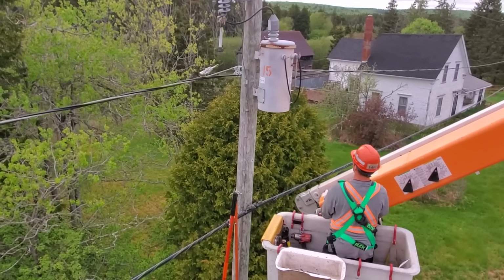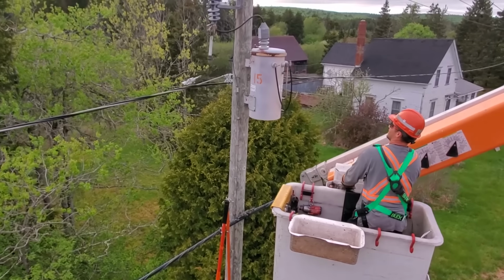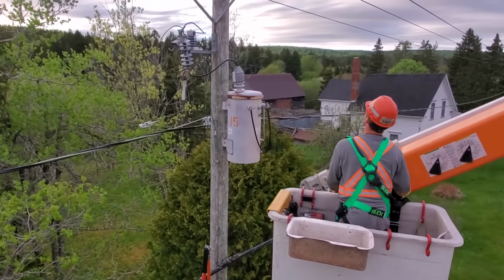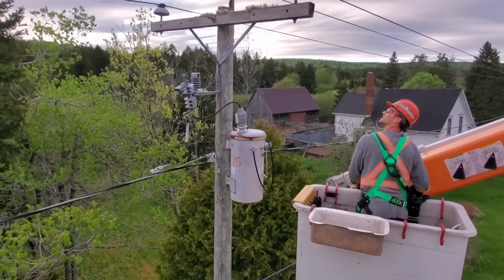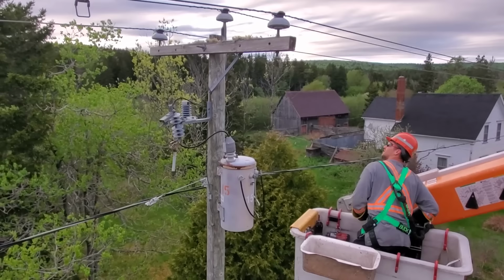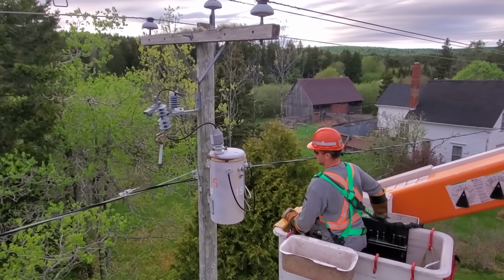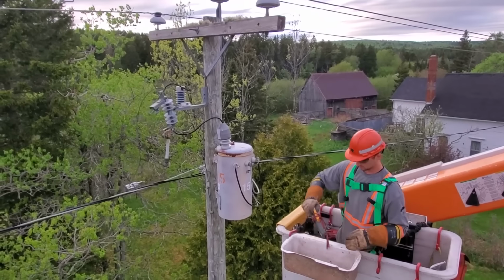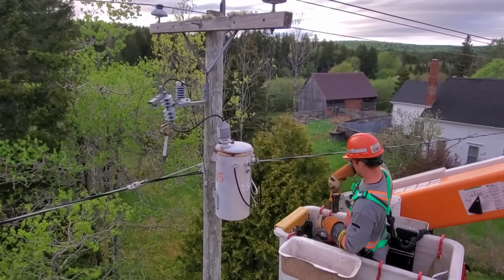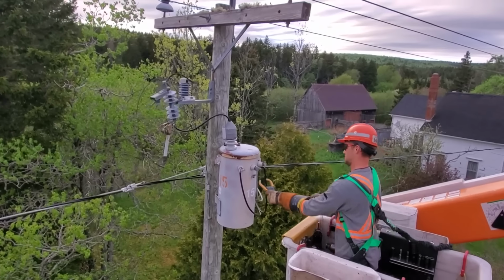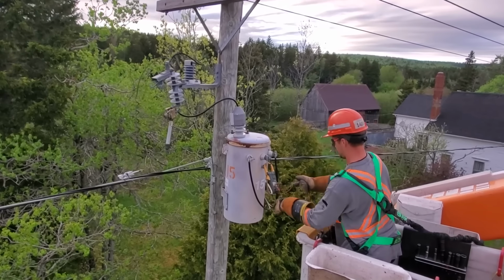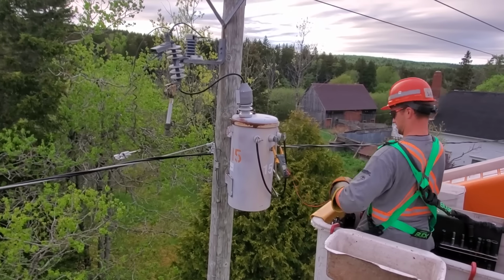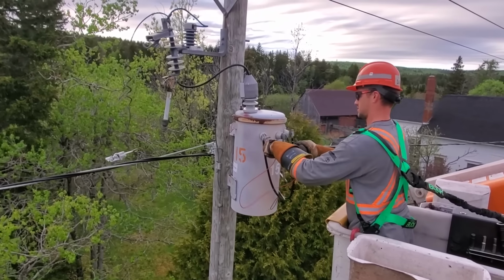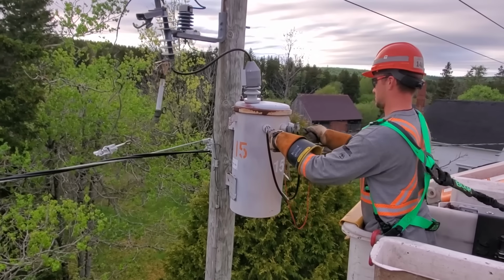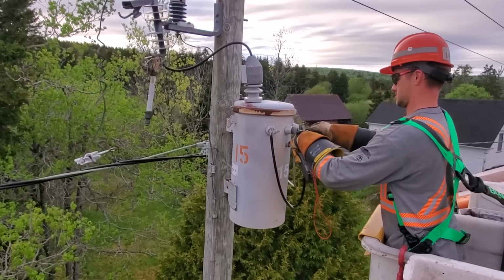So the next step he's going to take before he gets in there is double checking all the ties up on the crossarm, condition of the crossarm, make sure there's no hazards. Now, whenever we're working on a transformer, if there is any generators hooked up causing backfeed, the voltage will backfeed through the secondary side and step up to primary voltage.